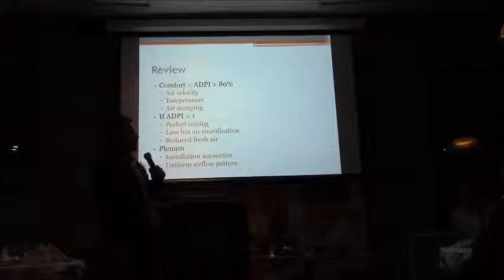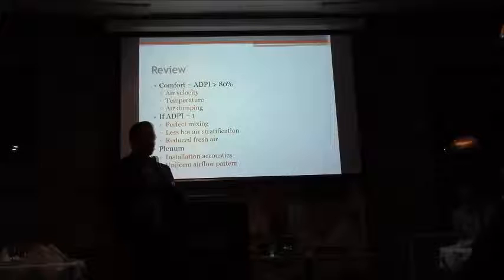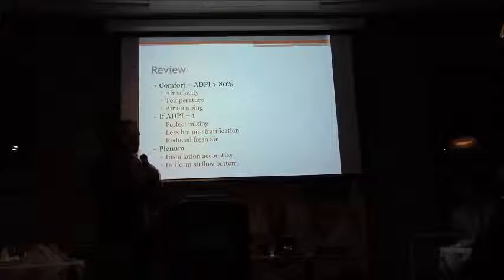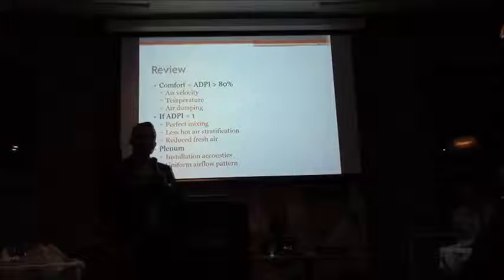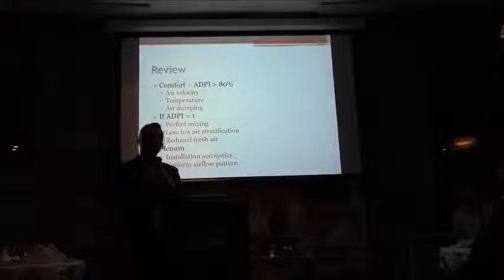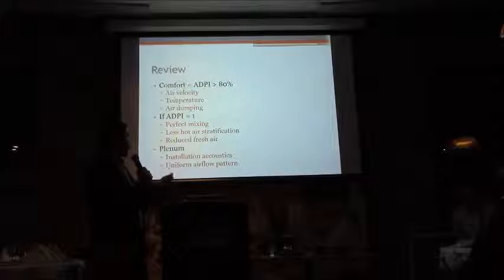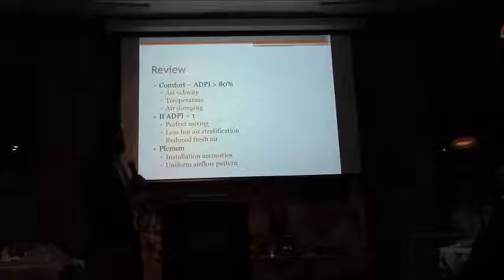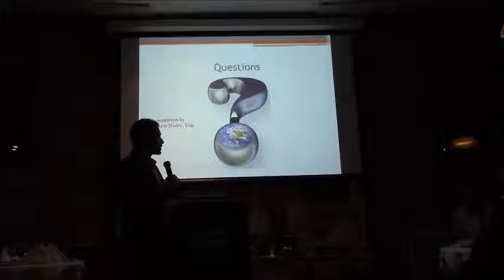And ideally, you always want to put a plenum on your diffuser. Whatever type of diffuser you're using, whether you're going with the cone, the high induction, linear diffuser, use a plenum because it's going to allow you to always keep the mentioned performances by the manufacturer. And you'll get a uniform airflow pattern. That's pretty much it.